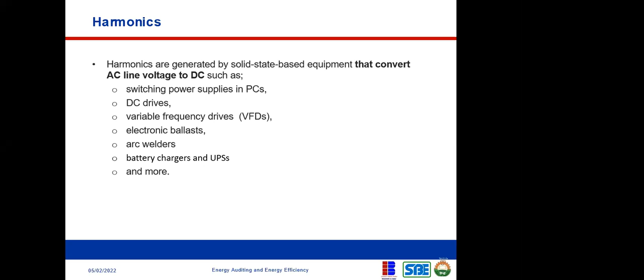Most power systems can accommodate a certain level of harmonic currents, but we experience problems when harmonics become a significant component of the overall load. As this higher frequency harmonic current flows through the power system, it can cause communication errors, especially now that we're talking about Industry 4.0, cloud computing, and the Internet of Things. Some of these things are connected to the power system, so when there are harmonics in the power system in which they operate, they can cause communication errors. They can also cause overheating of hardware and metering errors.